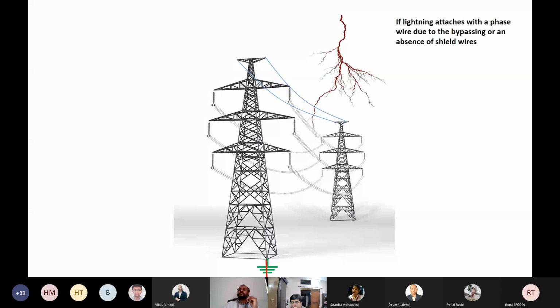Now, if lightning attaches to a phase wire due to the bypassing or an absence of a shielding wire, imagine that lightning current strikes straight into a live wire, either bypassing the shielding wire or in the absence of a shielding wire. What can you expect? In one way, there is a chance of the insulation failing at the nearest insulator, and the current will flow into the tower footing. But a sizable current still will go into the transformer as well.